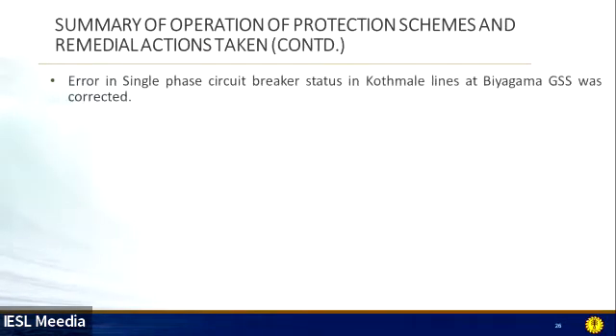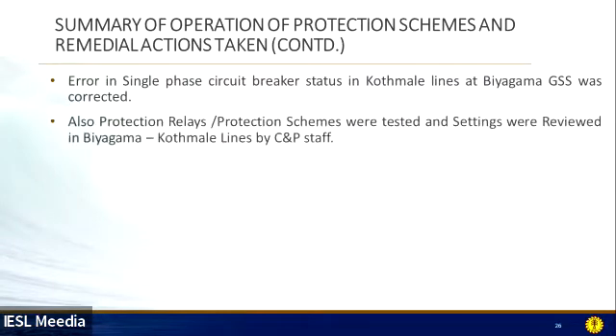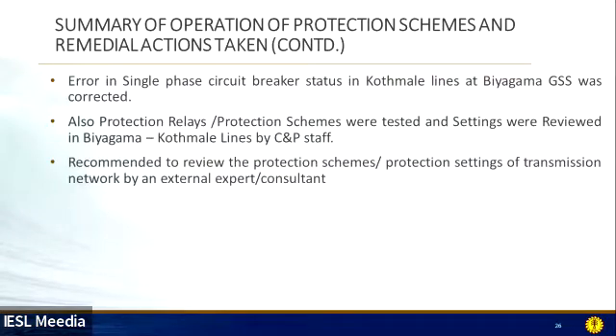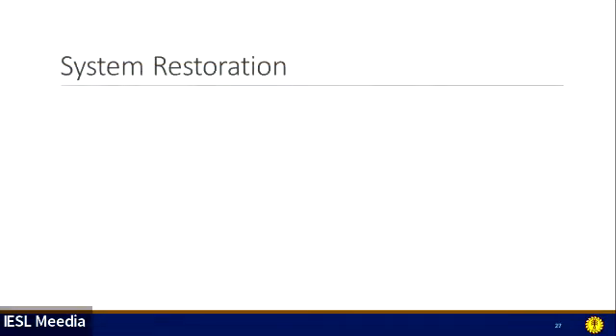The error in the single phase circuit breaker status of the Kotmale line at Biagama was corrected. This is to avoid incorrect operation of the end fault protection scheme. We have done proper wiring of the circuit breaker status to the busbar protection relay of Biagama. Also, protection relays and protection schemes were tested and settings were reviewed in the Biagama Kotmale line by control and protection branch staff. Again, the final recommendation is to review the protection scheme and protection settings of the transmission network by an external expert consultant.